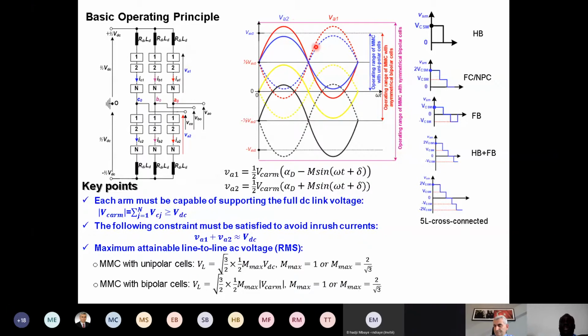This means we can operate with positive DC voltage at this point, or we can operate with negative DC voltage at this point. So this actually makes the VSC with full bridge cells well suited to operate with LCC type, because in LCC type, if you want to reverse the power flow, you have to reverse the DC voltage. While if you go with the middle ground, which is a cell with asymmetrical bipolar output, you extend the control range, but only from here to here.